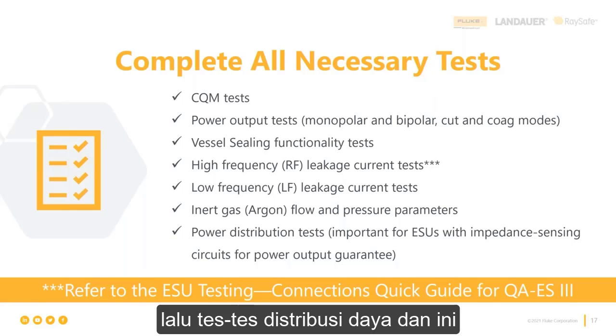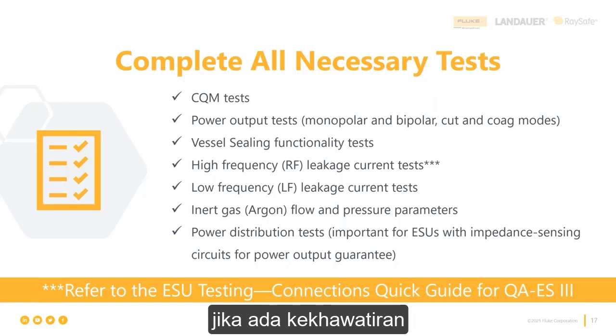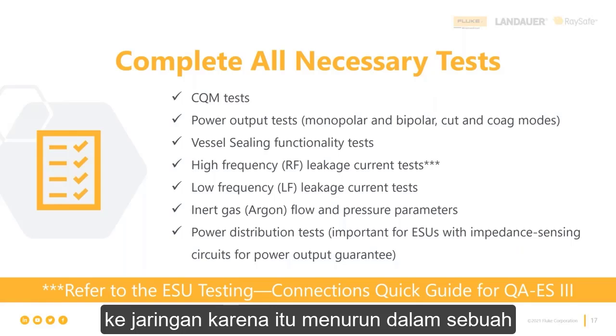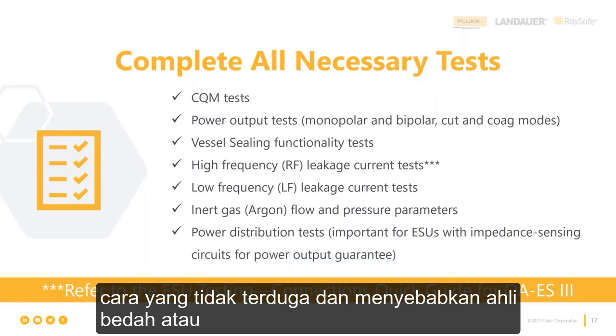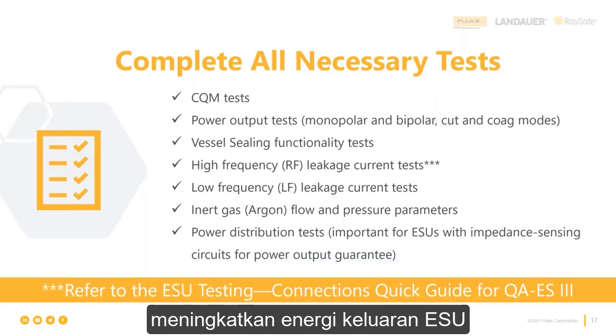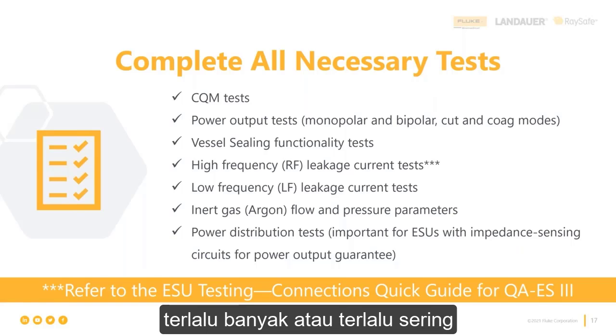And then power distribution tests, and these are important, especially if there's a concern that as the tissue resistance increases, the current flow and energy delivery to the tissue therefore decreases in an unexpected way and causes the surgeon or the circulating nurse to have to increase ESU output energy too much or too often. So there's this output energy guarantee functionality in some ESUs today. It's like impedance sensing. It's really sensing the impedance of the tissue by measuring the amount of current that has to be produced in order to achieve the power output setting on the ESU.